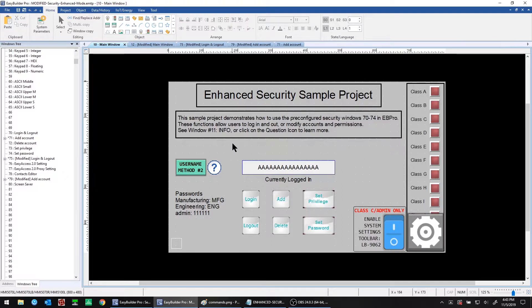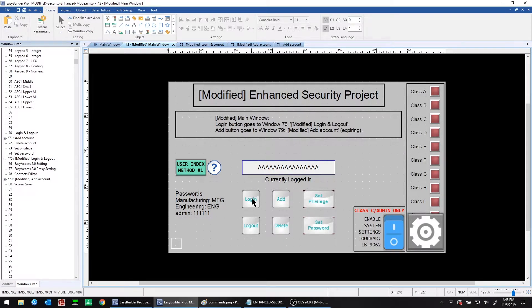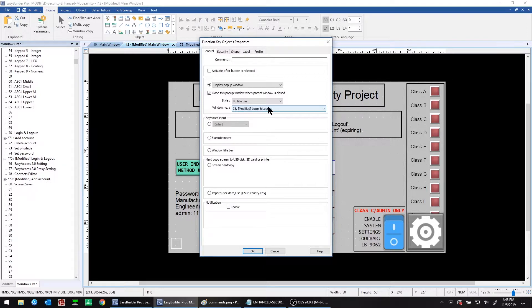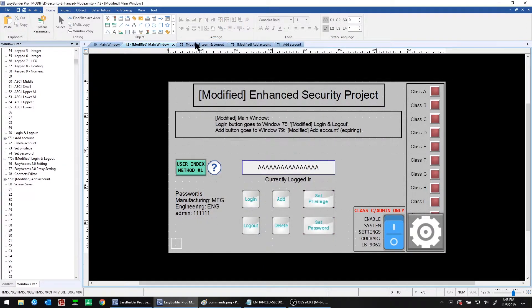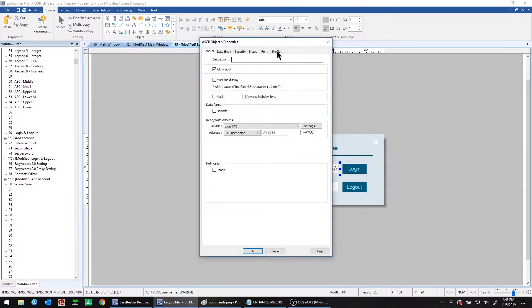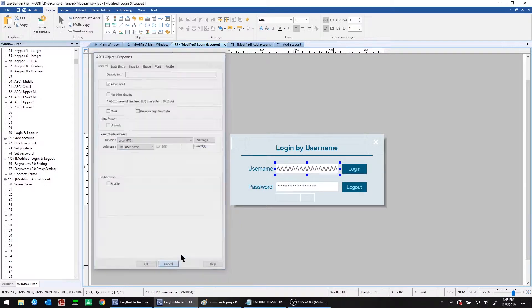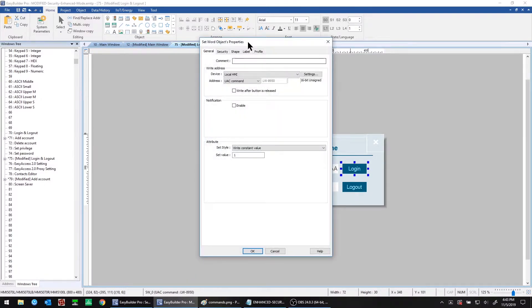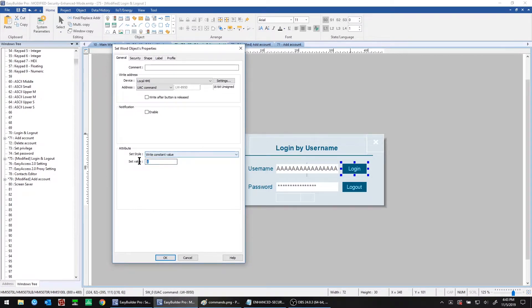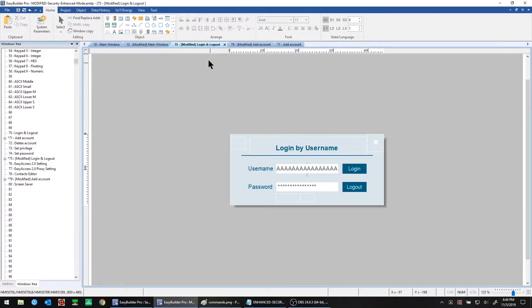We have another method for logging in. Besides using the user index, you can use a username method. We created a second main window with a login button that takes you to a modified login window — window number 75. To log in by username, instead of an option list, you set up an ASCII object and choose the UAC username address for the read and write address. The command value is different here too: use a value of 1 for logging in by username, versus 2 for logging in by user index.